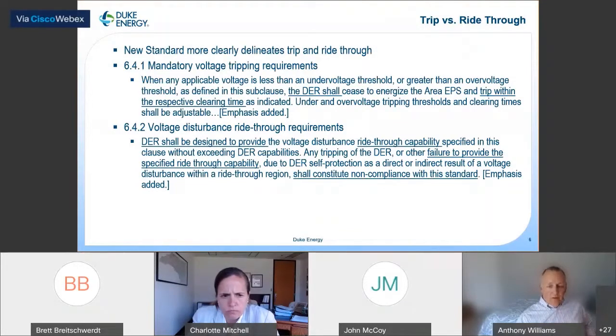The tripping requirement has always been here, but more emphasis has been placed on the capability to ride through disturbances for longer periods of time. So if we put these two together, the capability allows the inverter to continue to operate or ride through until the trip times are reached.